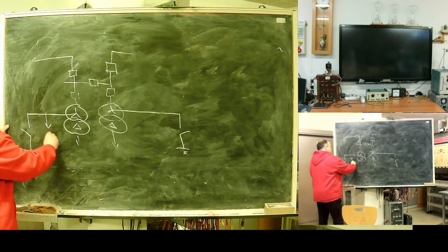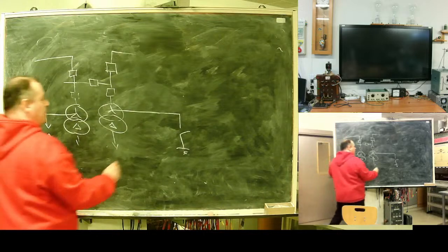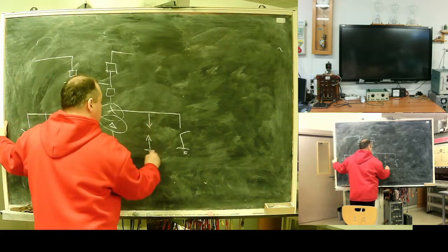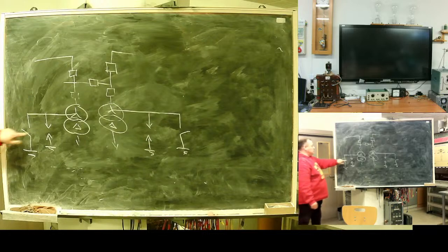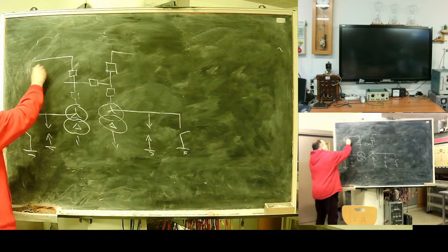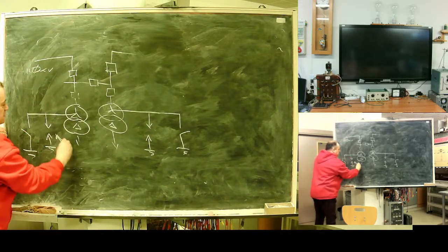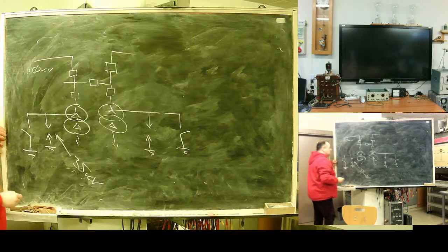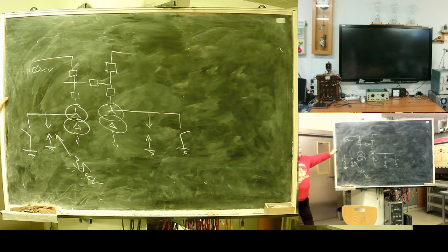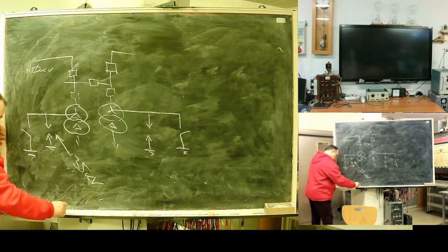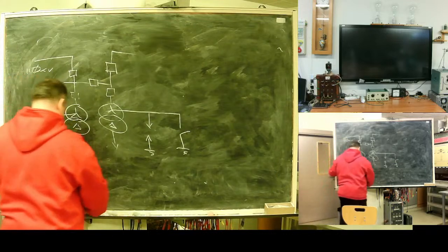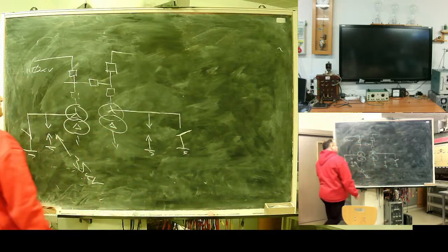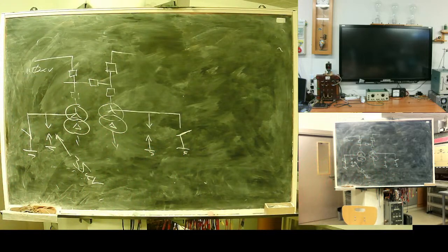These transformers are normally able to withstand 35 kilovolts voltage in the neutral. So, in normal mode, spark discharge, if this is a 110 kilovolt network, this will be for 45 kilovolts. Spark discharge. And only one of the disconnectors is on. Zero sequence resistance should remain constant.